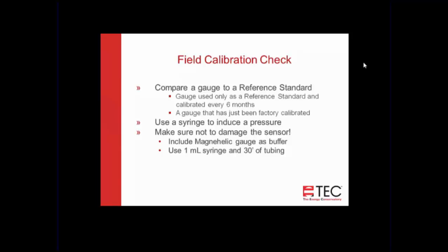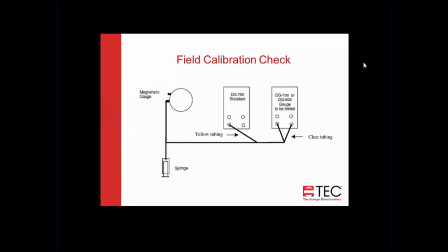And the DG700, the maximum pressure is about 1,200 pascals, and we're only testing at 500. So, if you're careful, you shouldn't have to worry about running over 500 pascals of pressure. So this is a basic field calibration check that's been in our manual for years and years, and it shows using the Magnehelic gauge and a syringe.